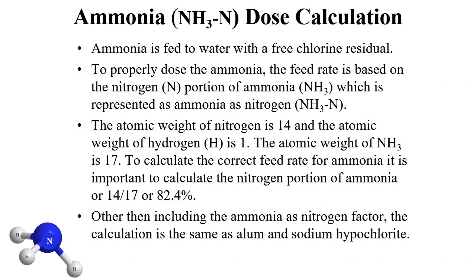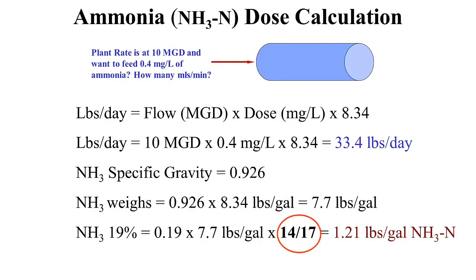Other than adding the ammonia-as-nitrogen factor, the ammonia feed rate calculation is the same as alum and sodium hypochlorite: pounds per day equals flow in MGD times milligrams per liter times 8.34. In this example, we determine the feed rate for a dose of 0.4 milligrams per liter at 10 MGD. Multiplying 10 times 0.4 times 8.34 gives 33.4 pounds per day. Ammonia has a specific gravity of 0.926 — lighter than water — weighing about 7.7 pounds per gallon. At 19% concentration, we add the 14/17 nitrogen factor to get 1.21 pounds per gallon.